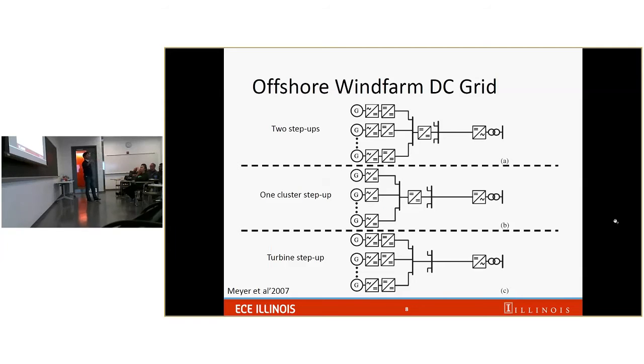But the problem with shifting the wind farm offshore is you cannot use the AC transmission line, because with the AC transmission line running under the sea, the cables are very close together, so the capacitance between the windings is high. If you transmit power under the sea for a long distance, you will see the voltage drop, and power delivery using AC with the sea cable for long distance is infeasible.